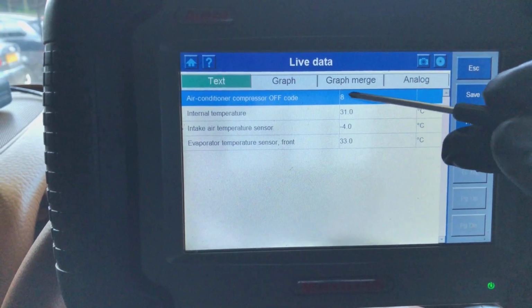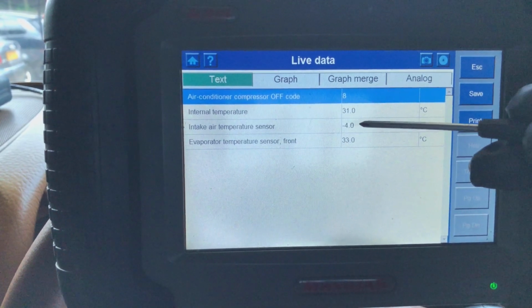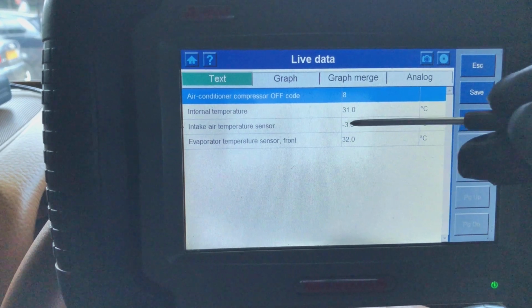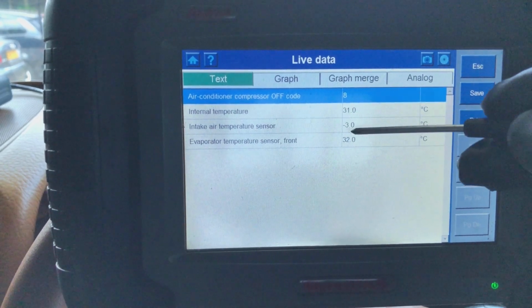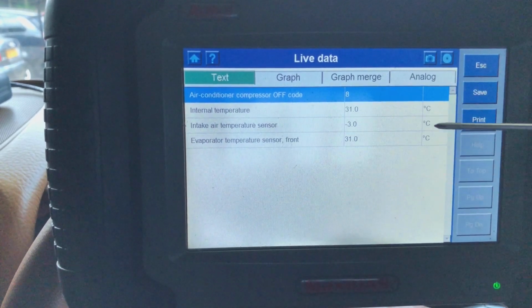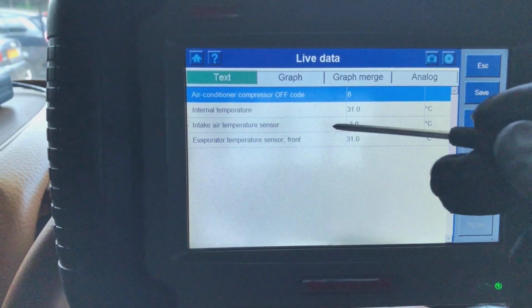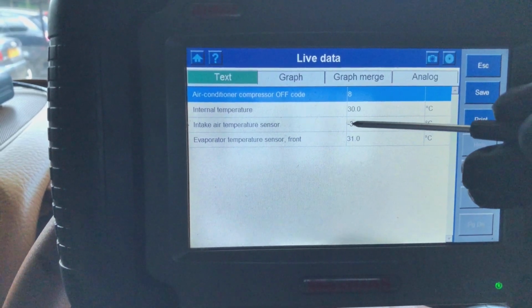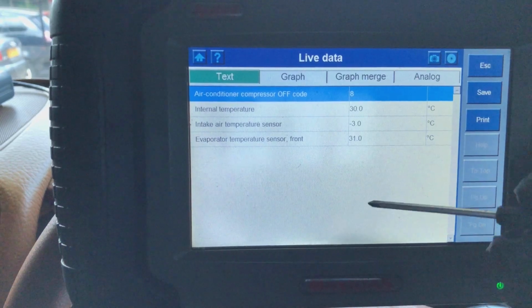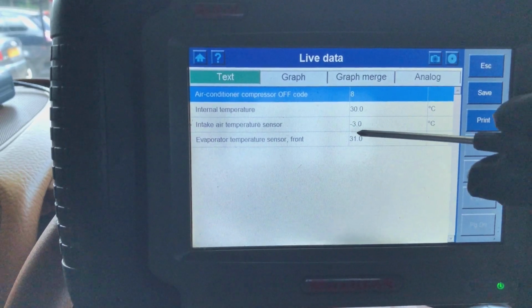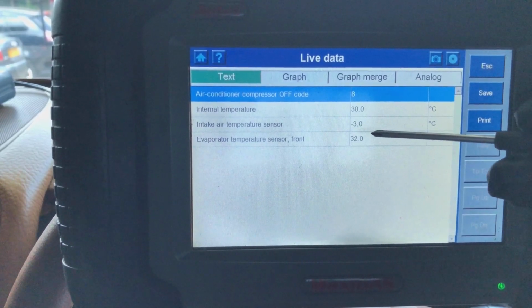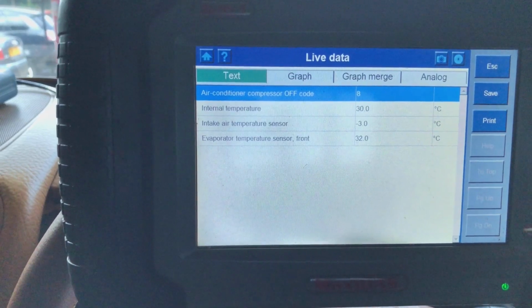And we have a code 8. Just like the manual says, we are not going to authorize the compressor because the outside temperature is too low. The outside temperature here is the temperature outside the evaporator, so this literally thinks the cabin is -3 degrees centigrade.